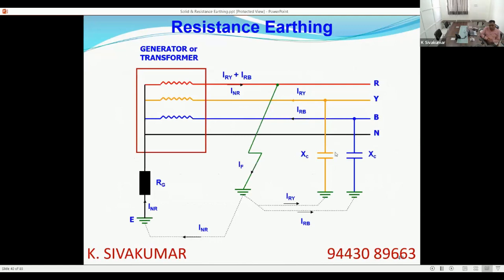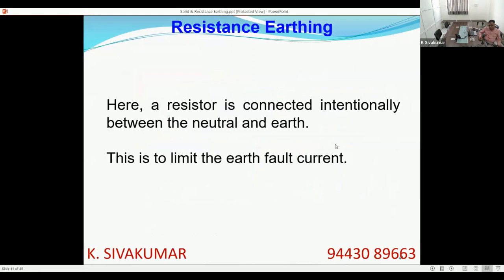The schematic is something like this. Compared to the solid earthing drawing seen, here you can see a black body between the neutral and the earth. The black rectangle is the neutral resistor, the ground resistor. RG is the NGR, neutral grounding resistor. So here also there will be a capacitive current contribution, but as seen, it is almost negligible. It is less than 5 ampere in the case of LV systems and less than 25 ampere in the case of medium voltage and high voltage systems. So here a resistor is connected intentionally between the neutral and the earth. The purpose is to limit the earth fault current.